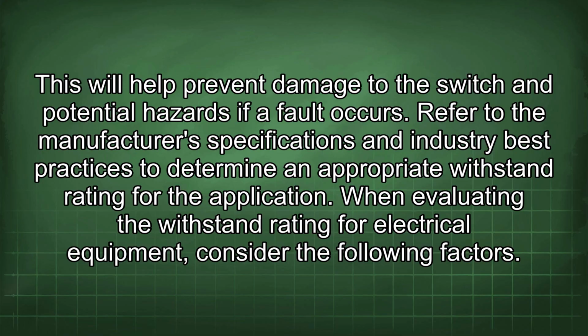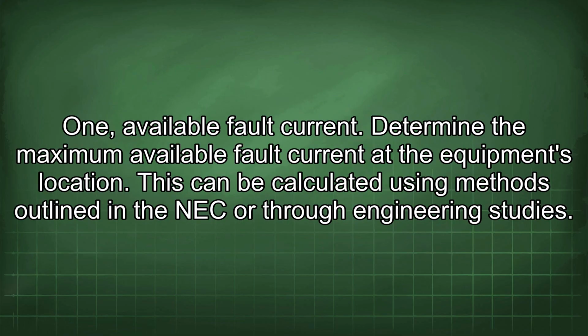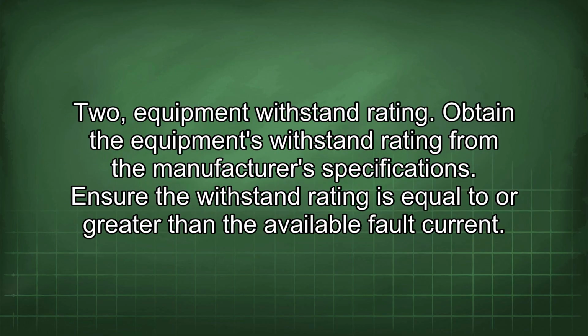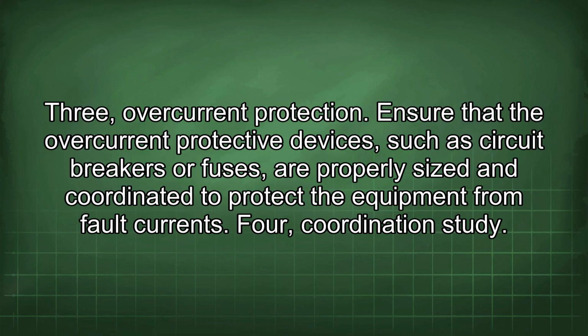When evaluating the withstand rating for electrical equipment, consider the following factors. 1. Available fault current. Determine the maximum available fault current at the equipment's location. This can be calculated using methods outlined in the NEC or through engineering studies. 2. Equipment withstand rating. Obtain the equipment's withstand rating from the manufacturer's specifications. Ensure the withstand rating is equal to or greater than the available fault current. 3. Overcurrent protection. Ensure that the overcurrent protective devices, such as circuit breakers or fuses, are properly sized and coordinated to protect the equipment from fault currents.